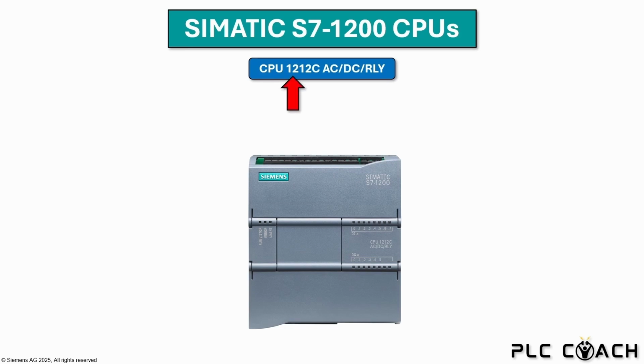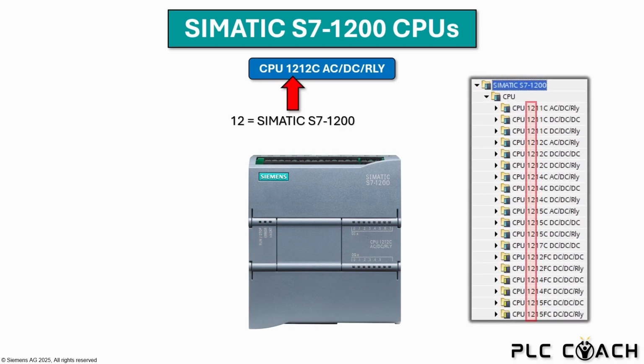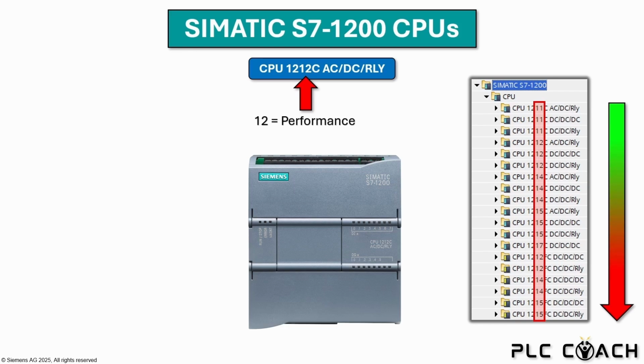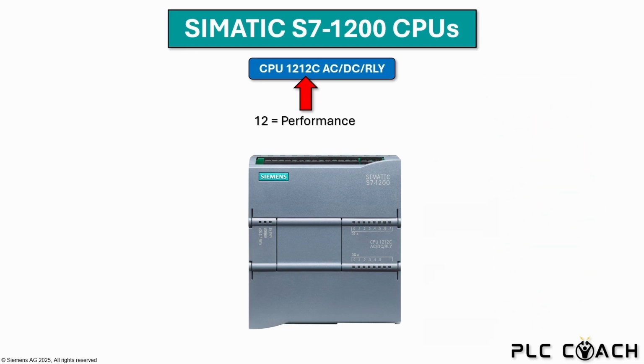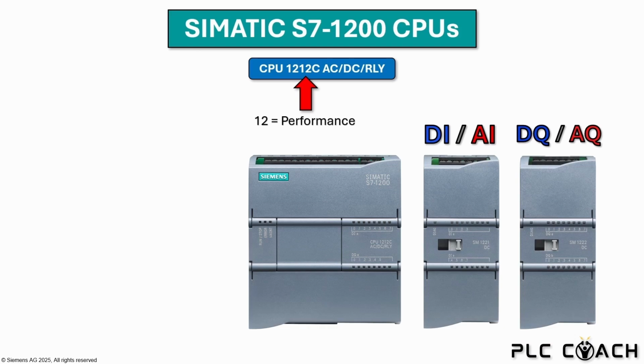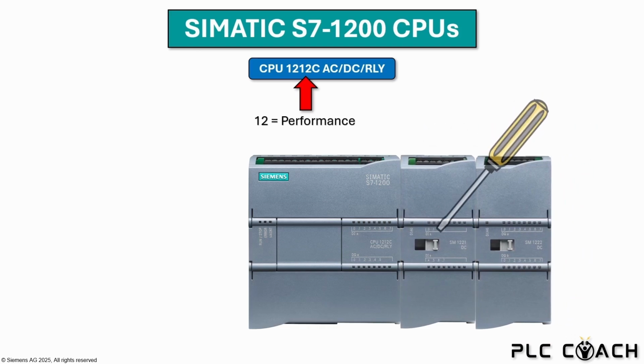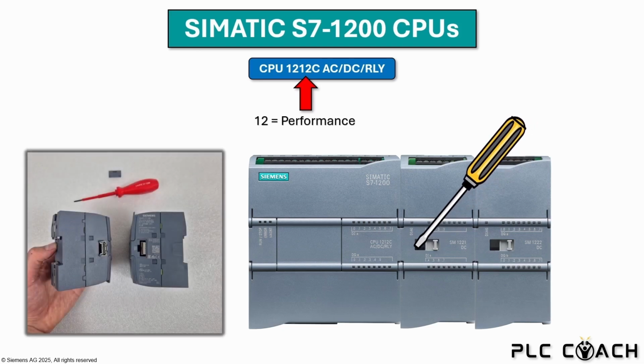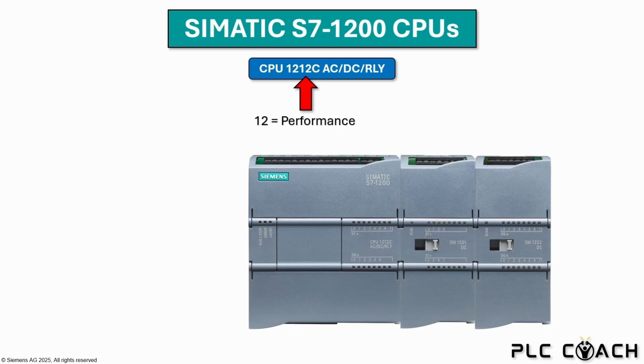The first 2 digits again represent the generation of the controller. In our case, it's a Simatic S7 1200. The second 2 digits describe the performance and expandability. For example, a CPU 1211 cannot be expanded, while the CPU 1212 can. The CPU 1212 has less work memory than the CPU 1217. You can find details about this in the manual of each controller. There are also digital and analog expansion modules for the S7-1200. These are placed to the right of the CPU and connected to each other by using the built-in bus connector. By the way, the S7-1200 is not mounted on a special rack, but on a simple DIN rail.